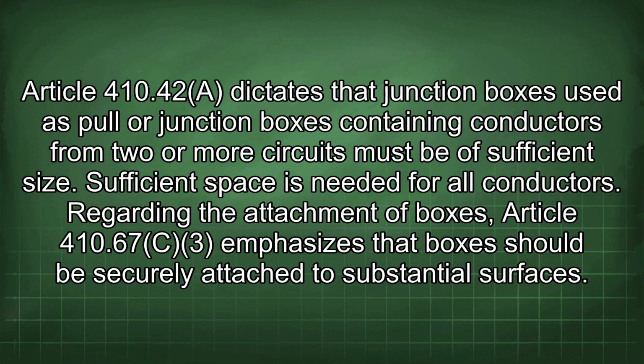Article 410.42 dictates that junction boxes used as pull or junction boxes containing conductors from 2 or more circuits must be of sufficient size. Sufficient space is needed for all conductors. Regarding the attachment of boxes, Article 410.67c3 emphasizes that boxes should be securely attached to substantial surfaces.